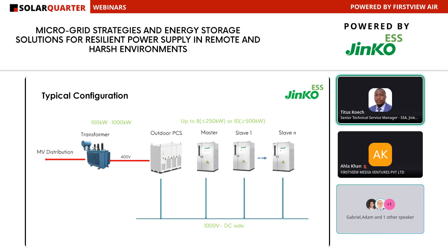Then we have the DC busbar, provided in the DC Confluence cabinet. We can have the output of the PCS at 400 volts, that is low voltage, and we can also have provision for a step-up transformer to medium voltage distribution.